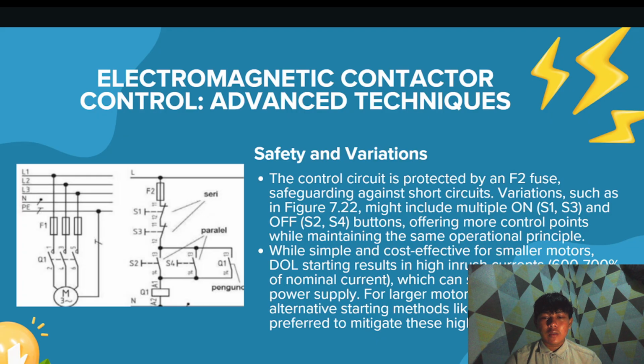While simple and cost-effective for smaller motors, DOL starting results in high inrush current, 600 to 700% of nominal current, which can stress the motor and power supply. For large motors, 10 kilowatts to 50 kilowatts, alternative starting methods like star-delta control are preferred to mitigate this high starting current.